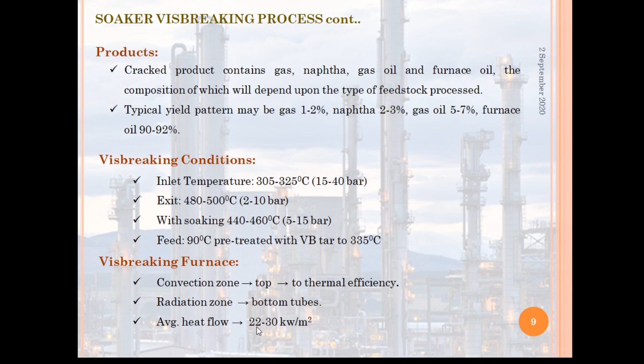So in this visbreaking furnace, what will happen? In this furnace there is a convection zone, and a radiation zone. The convection zone is at the top of the furnace, where it gains the thermal efficiency, and the radiation zone is situated at the bottom of the furnace, where the tubes are. The average heat flow in the visbreaking furnace is 22 to 30 kilowatt per meter square.